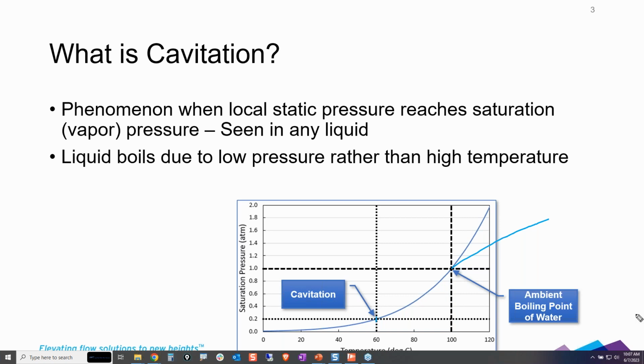So when you're dealing with a Waterhammer or a transient situation, high pressures are not the only thing to be concerned about. Low pressures can be just as bad, if not worse, because when you start cavitating and it causes vapor volumes to form in your system, that's going to be a real issue.